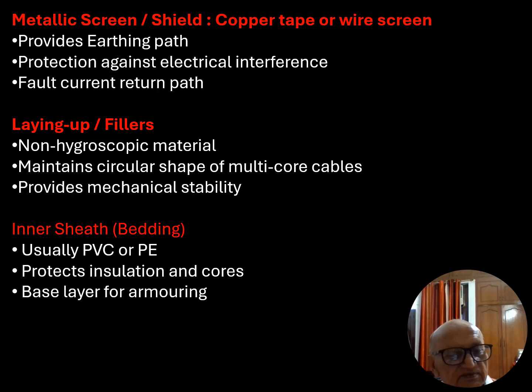Then in case of MV armored cable, laying up or fillers. Fillers are provided to fill up the gap to make the shape circular. The filler quality has to be non-hygroscopic material. It maintains circular shape of multi-core cables, provides mechanical stability.